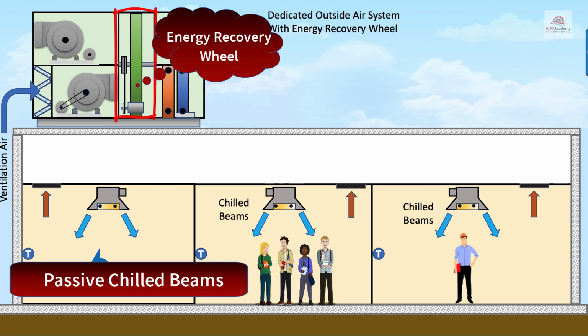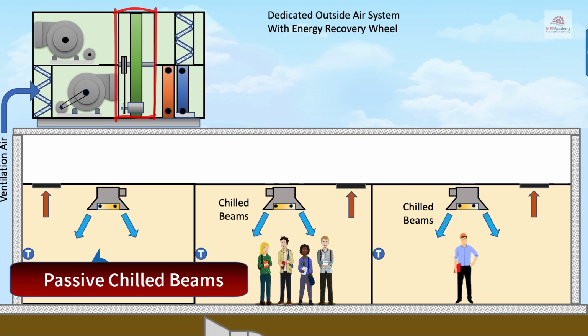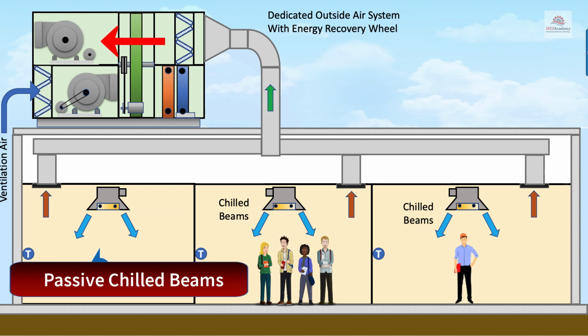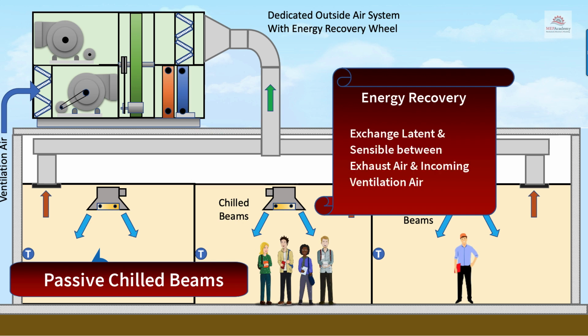The energy recovery wheel is used to capture energy from the air being exhausted from the space and returning this energy to the air entering the unit. Remember, the DOAS unit is 100% outside air. So that means the exhaust air volume needs to be close to the quantity of ventilation air coming into the building to avoid overpressurizing the spaces. Energy recovery is the process of exchanging sensible and/or latent heat between the exhaust air and outside air airstreams. Where extreme outdoor temperatures and relative humidities exist, the use of energy recovery devices can increase energy savings by capturing the energy before it is exhausted.